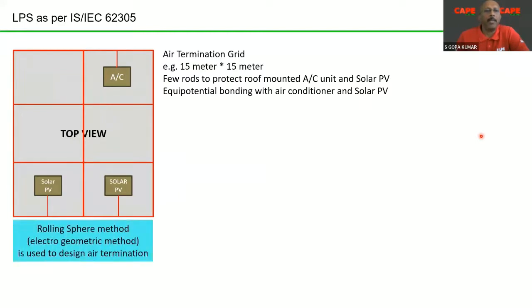The second part is down conductor. As I said, the rolling sphere or the electrogeometric sphere is used to design or to position the air termination system. Air termination is not a protecting technology or protecting technique, it's not a component. It's a technique to find out the probable place of lightning strike. The second part is down conductor.